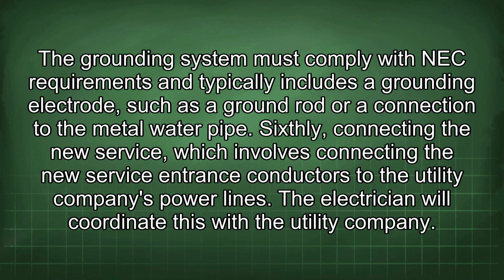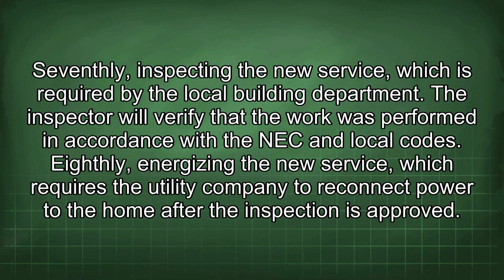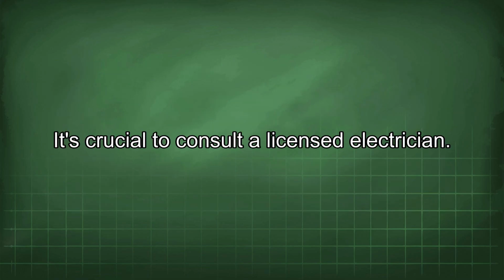Sixthly, connecting the new service, which involves connecting the new service entrance conductors to the utility company's power lines. The electrician will coordinate this with the utility company. Seventhly, inspecting the new service, which is required by the local building department. The inspector will verify that the work was performed in accordance with the NEC and local codes. Eighthly, energizing the new service, which requires the utility company to reconnect power to the home after the inspection is approved. It's crucial to consult a licensed electrician.